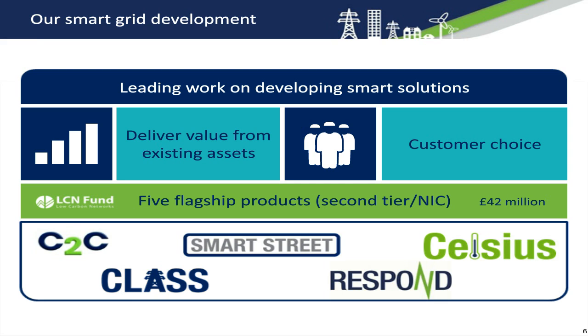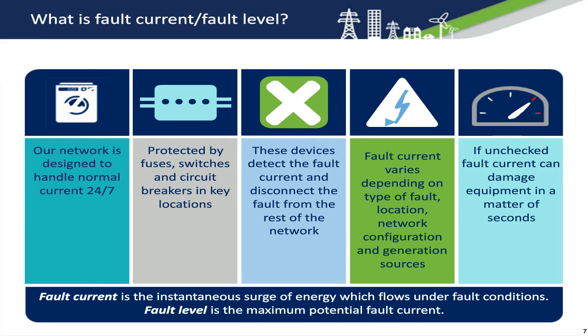So what is fault level? Our network is designed to handle normal current 24 hours, 365 days a year, and is protected by circuit breakers and other devices at key locations. When a fault occurs on the network, fault current surges towards the point of the fault from all sources of generation. This fault current is much greater than normal current and places stress on all electrical equipment it flows through. The protected devices react quickly, so the fault is disconnected from the sources of the generation.